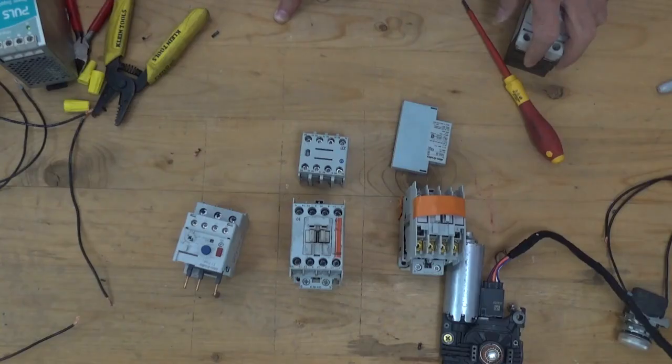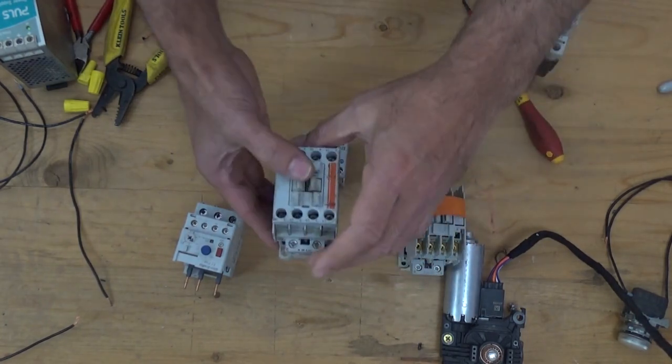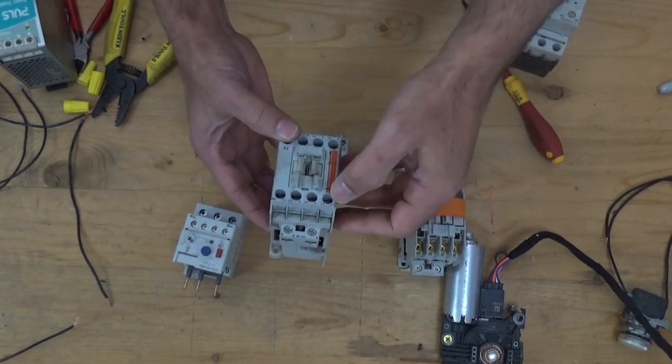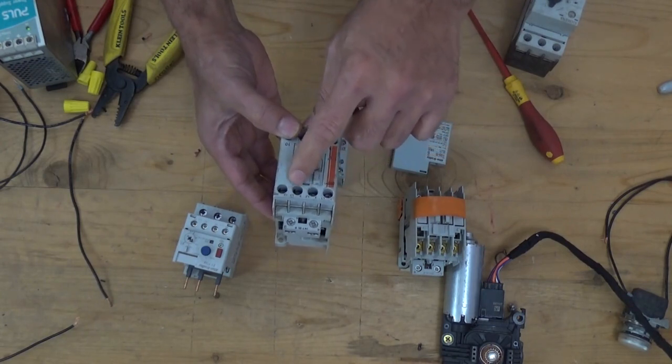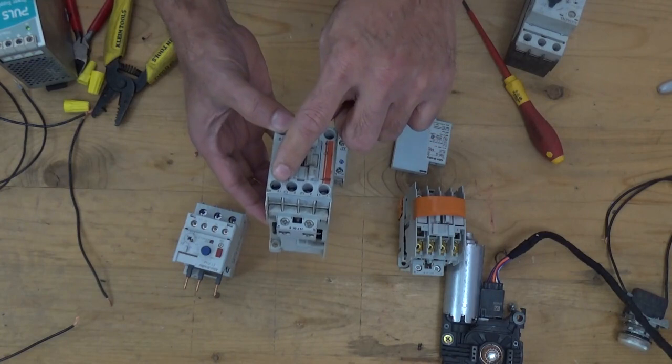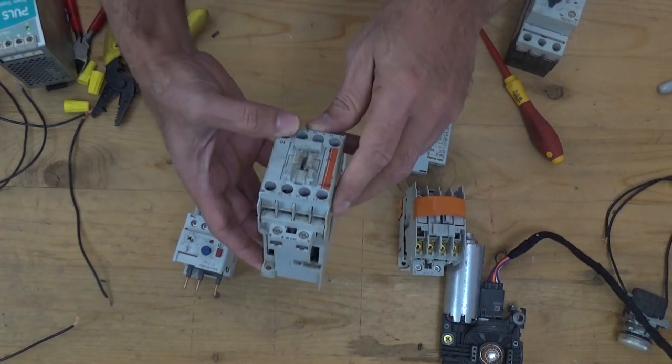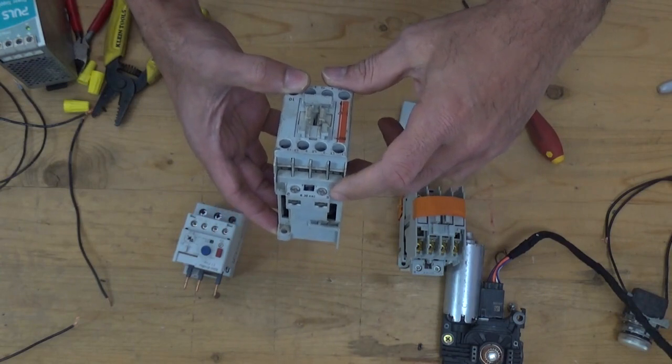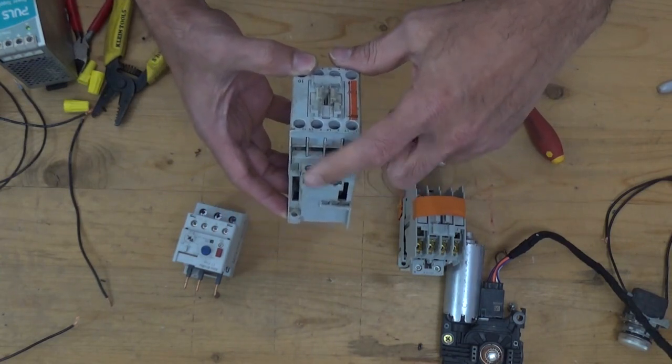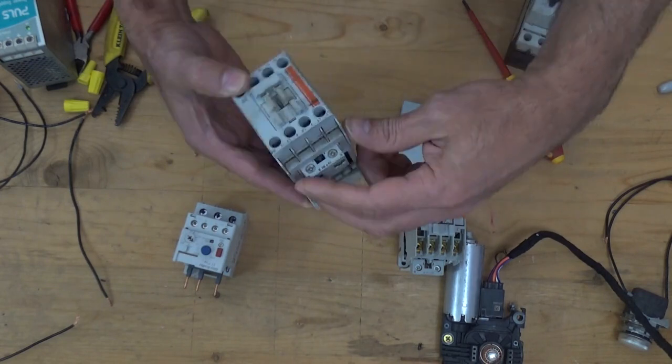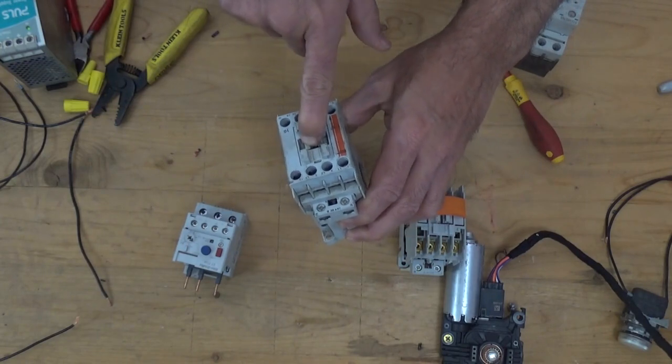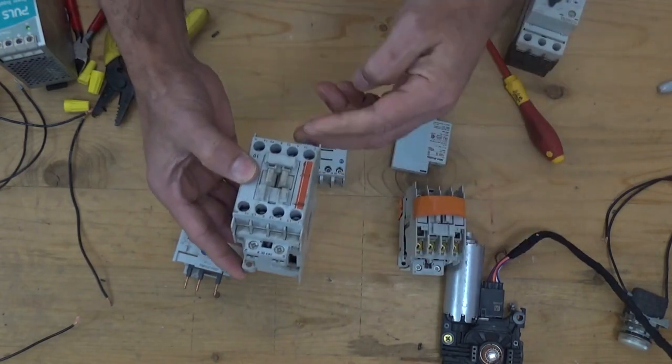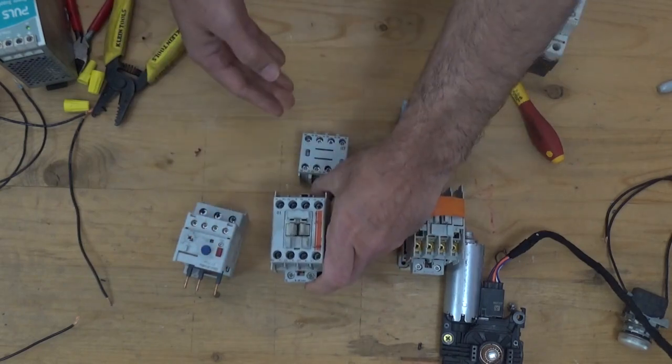Hey guys, today we're going to discuss motor contactor and overload relay inner parts. This is the magnetic contactor. This is line one, line two, line three, or one, three, five. On the bottom side, we have A1 and A2. This is our coil. When we supply this one, the plunger here will be pushed down. The plunger here will be pushed down, passing from line one to T1.